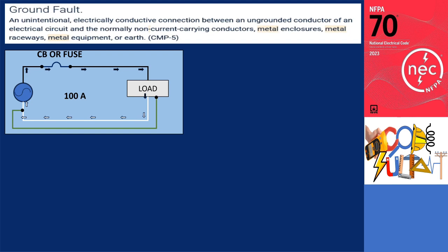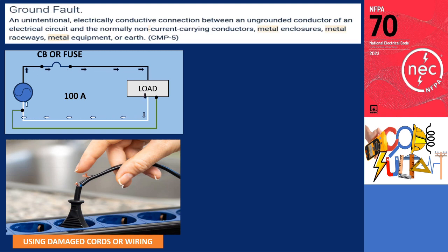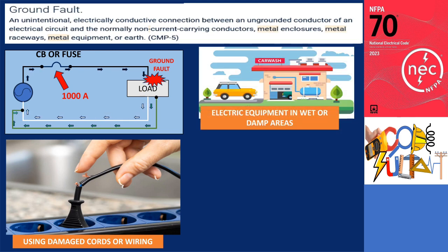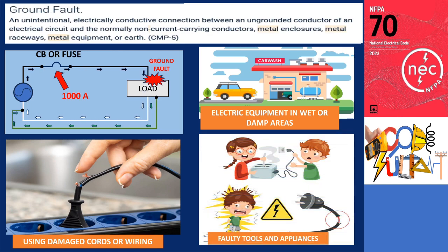A ground fault is an unintentional, electrically conductive connection between an ungrounded conductor of an electrical circuit and the normally non-current carrying conductors, metal enclosures, metal raceways, metal equipment, or Earth. As shown in the illustration, if a circuit with a 100 ampere load is connected, one of the causes of ground fault is damaged insulation in conductors. Once a damaged conductor touches the metal parts of any equipment, a ground fault will occur. Other causes of ground fault include electrical equipment in wet or damp areas and faulty tools and appliances.